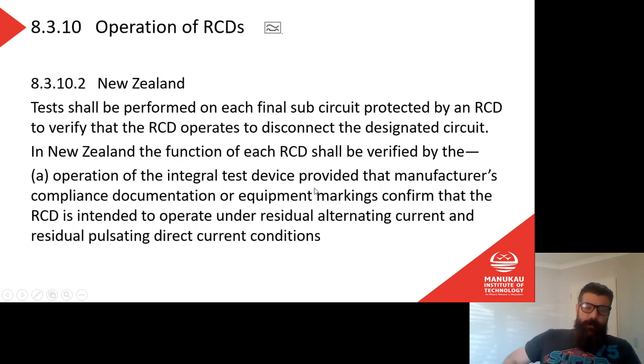Operation of RCD. An RCD is another type of safety device. We talked about circuit breakers very briefly. I think we've mentioned before that you get portable RCDs on extension leads. These days, it's the requirement that any new sub-circuit that's installed or any new build must have RCDs protecting everything. So we're going to see RCDs a lot in switchboards. When we install an RCD, we need to test that RCD works, and that's RCD testing essentially.